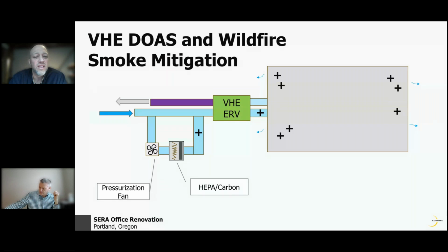And we've got a VHE DOAS system, but instead of just stacking up the VHE DOAS with a bunch of filters, inside or before, we actually install the pressurization, sort of a bypass loop, and HEPA and carbon filtration. And so the idea here is we look at the outside air, and when the PM 2.5, particulate matter 2.5 micron in size, gets up beyond a certain threshold, we engage the wildfire smoke system. And what this does is it pressurizes the building so that infiltration isn't allowed in, but it also forces dedicated outside air through really fine filtration and carbon to get rid of smells from the wildfire smoke. And then delivers it to the space. And this happens automatically with the control system designed.